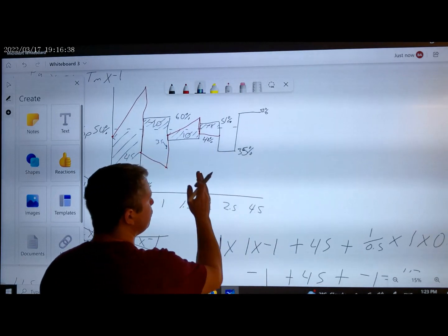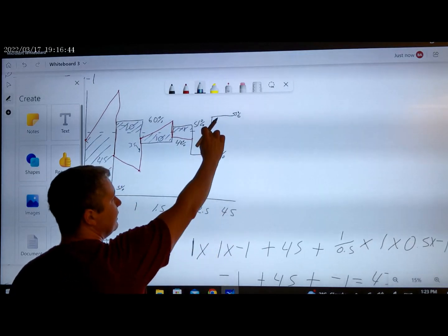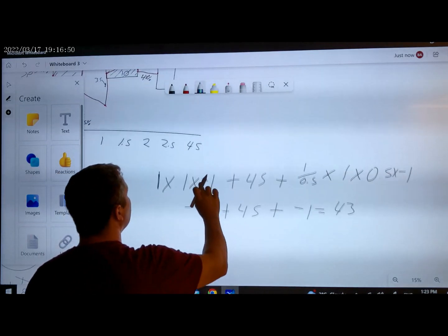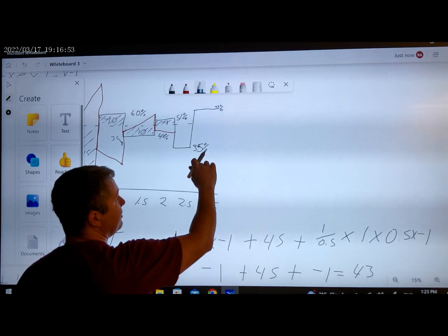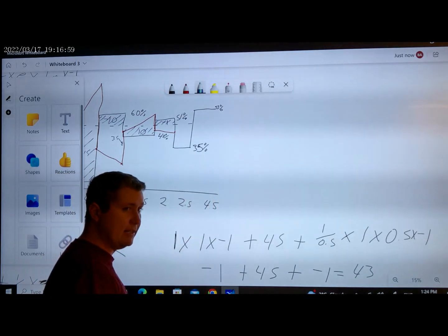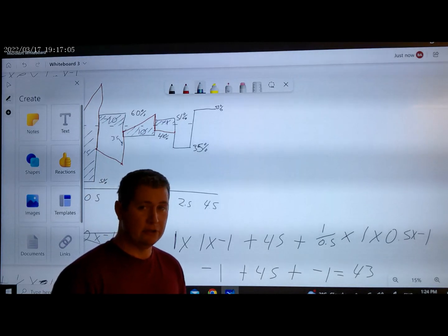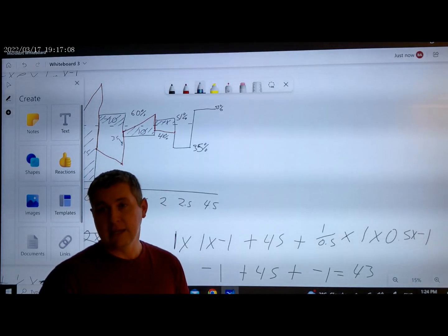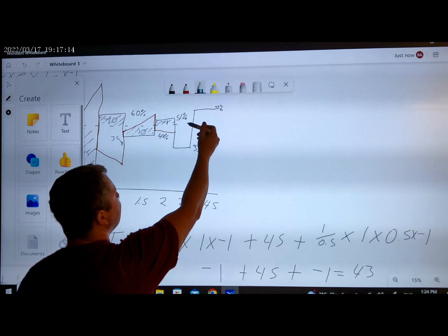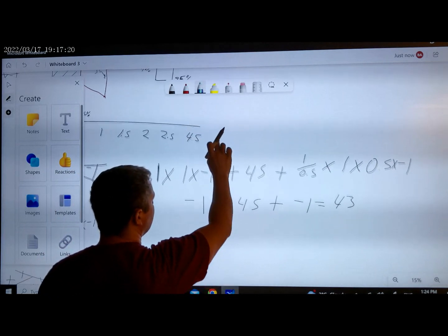Okay, so at the 2-minute mark, what happens when it passes the 2-minute mark? Our process variable dropped down. We're expecting our output to jump up. So our process variable of 35% gives us an error. And I keep saying this because in the lab, you're going to notice that sometimes I give you the error, and other times I give you the process variable. And when you know the process variable, you know the error, but you have to calculate the error by saying it is below the set point by 15, which means I have a negative 15 error.